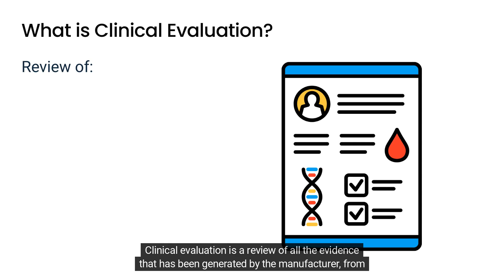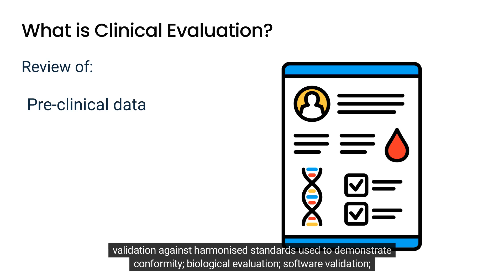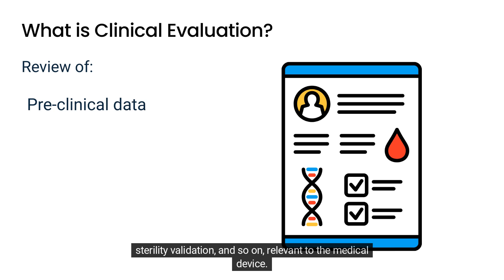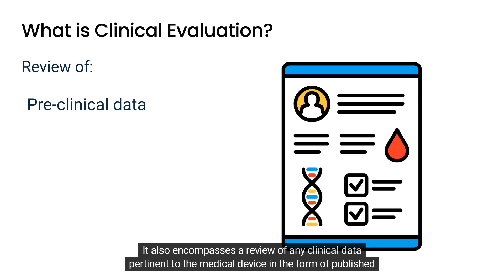Clinical evaluation is a review of all the evidence generated by the manufacturer from verification and validation activities in the design and development phase and manufacturing phases, including validation against harmonized standards used to demonstrate conformity, biological evaluation, software validation, sterility validation, and so on, relevant to the medical device.